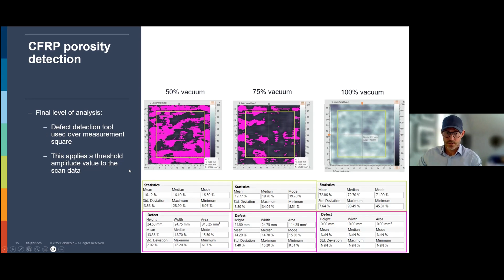Through transmission ultrasound, which is quite easy to use. As you can see here, that's when you put two transducers next to each other. And this is easy because you have a footprint that is about 32 by 32 millimeters. And to find this on each side of a composite is easier than with a probe, right? So with a probe, you have one little signal and you have to look at a single element probe. You have to look for that A scan and see if the A scan is big enough and say, okay, we're aligned. And then you move along. Let's say you have two people because this piece is huge and you cannot find the other person holding the other probe. But for MXTTU, this makes this procedure much easier because if you're aligned a little bit, you can easily align the rest of the transducer.